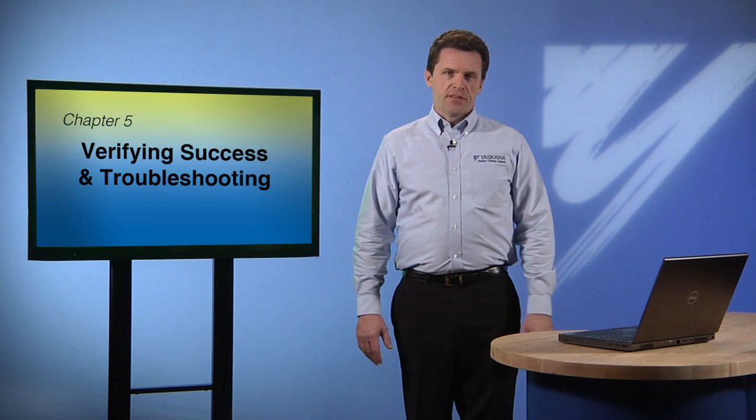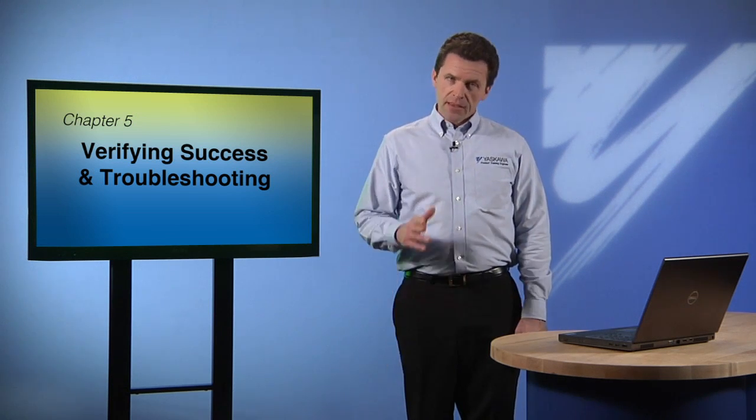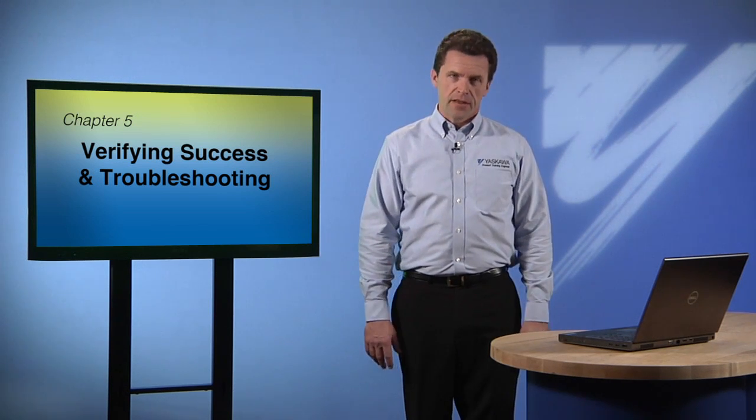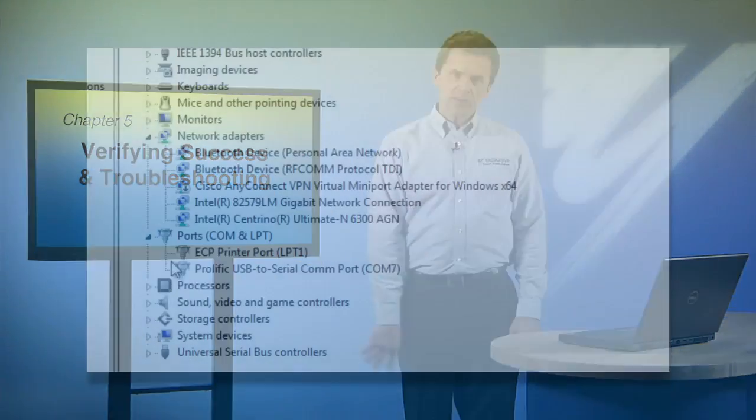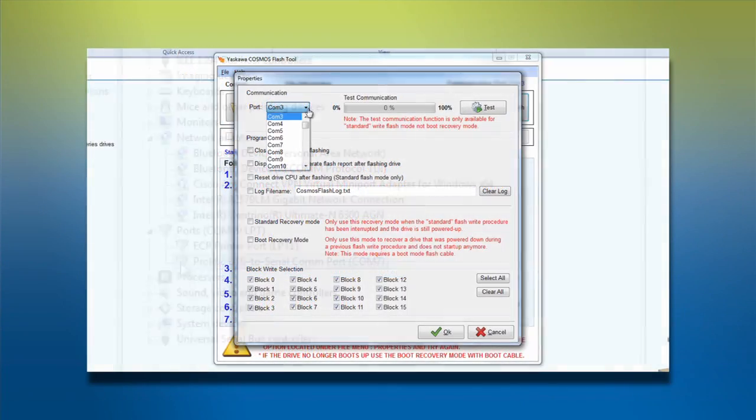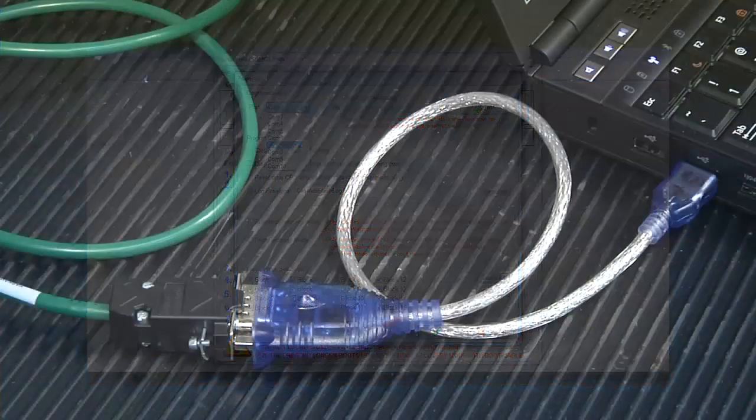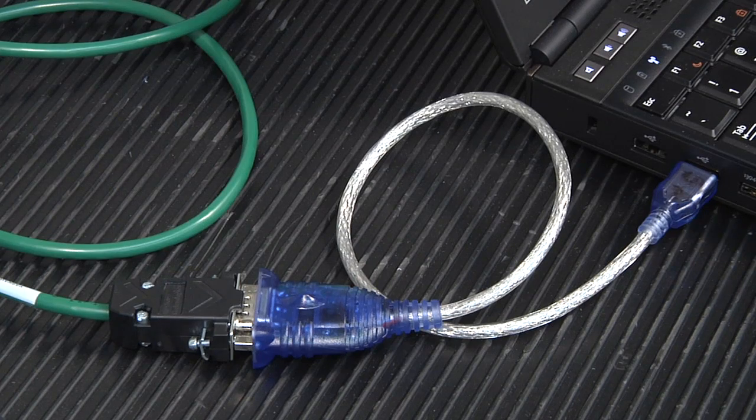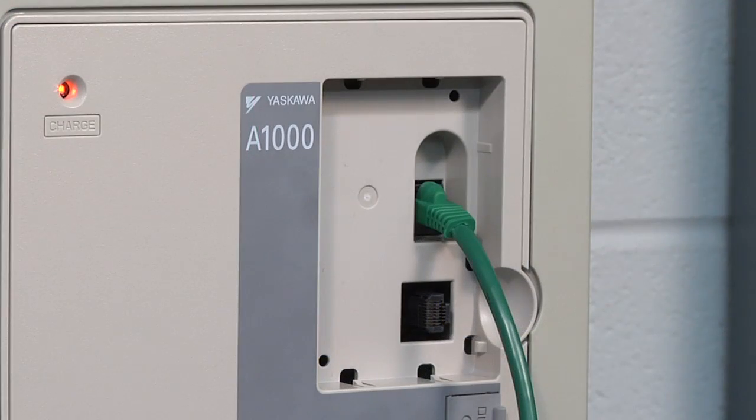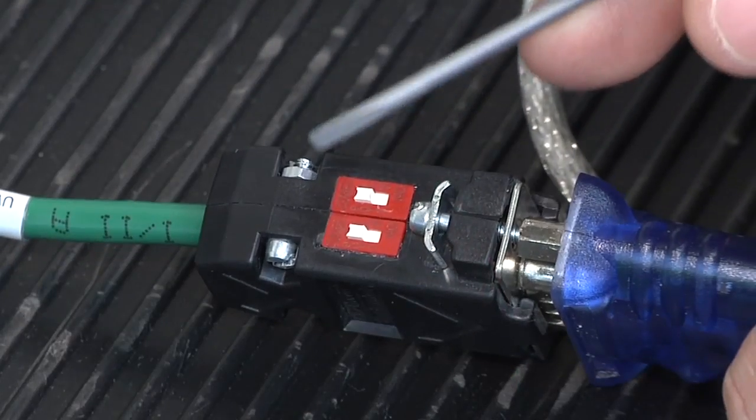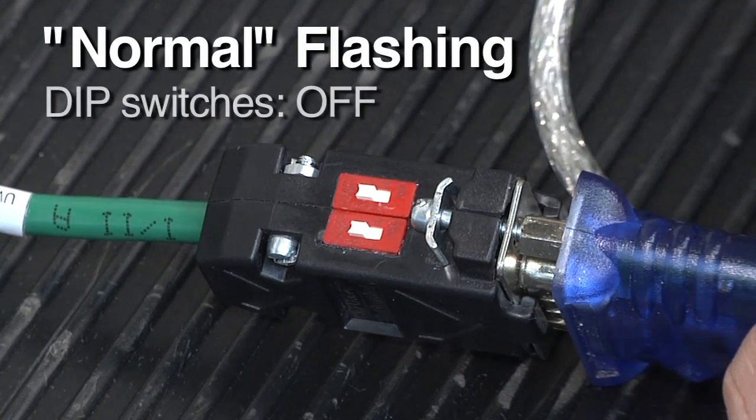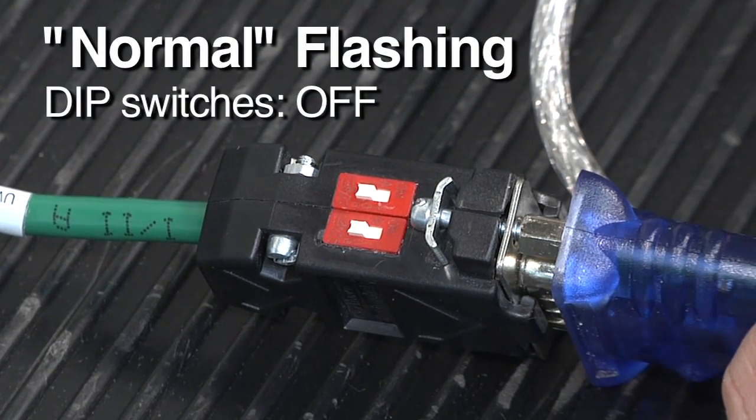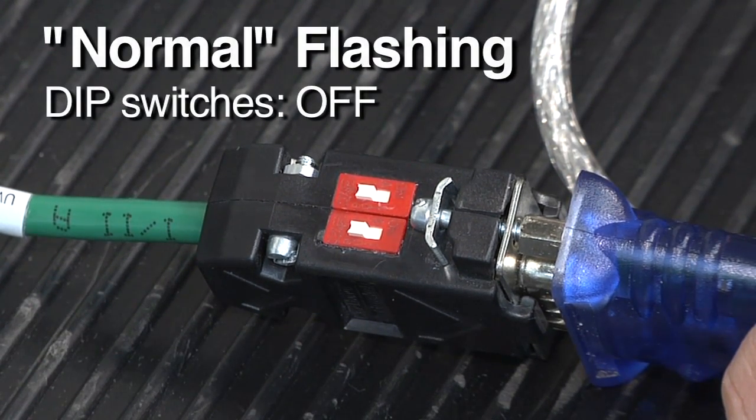If the Flash process doesn't complete successfully, here are a few things you'll want to check to find out why. Check to make sure the COM port number is correct. Also, look at the cable connections on both computer and the drive to be sure that they are properly seated. Check the DIP switches on the connection cable as well, making sure that both switches are flipped into the OFF position for normal flashing.